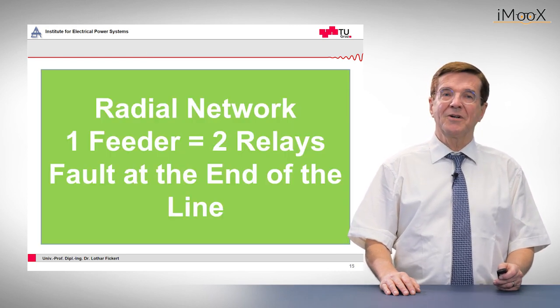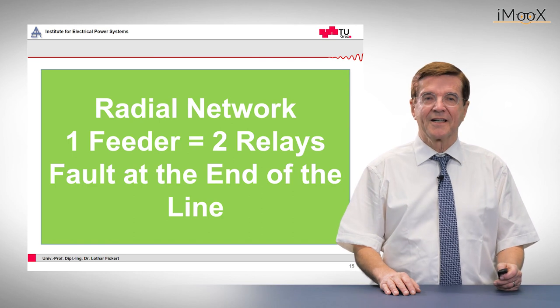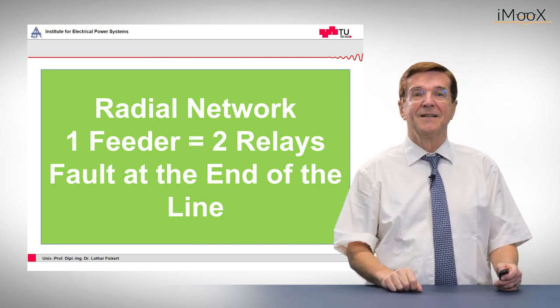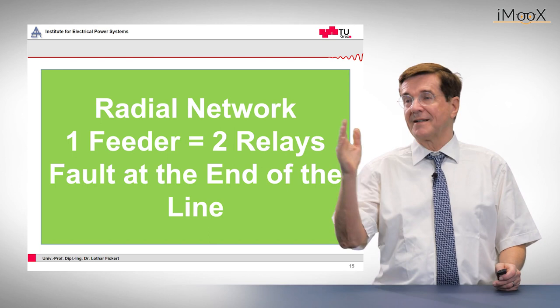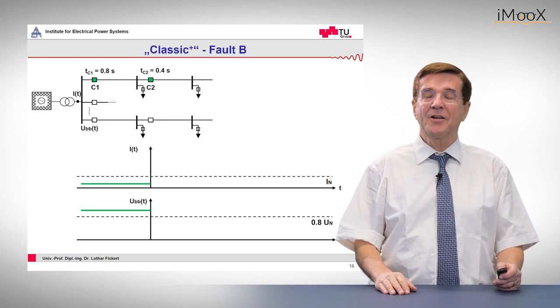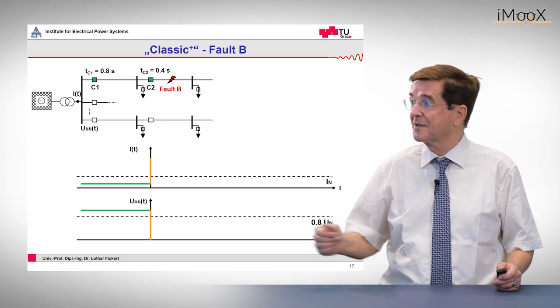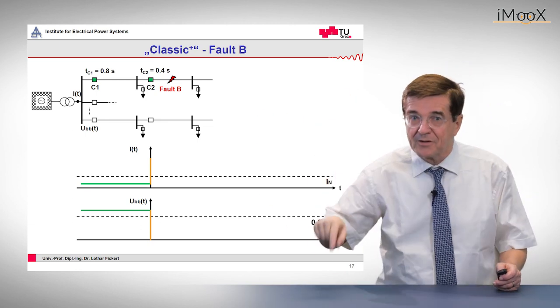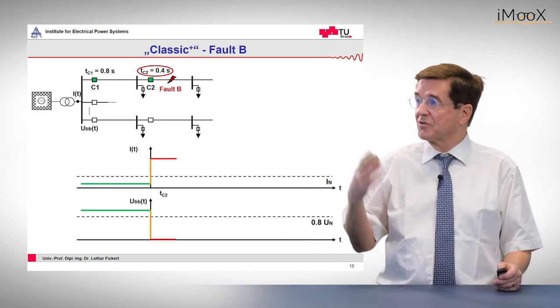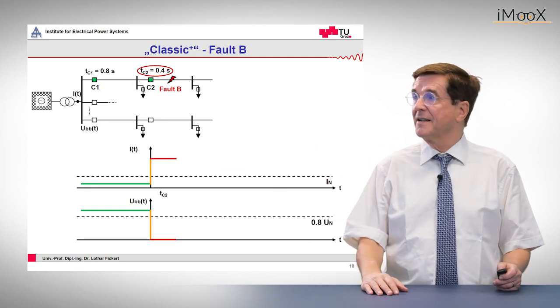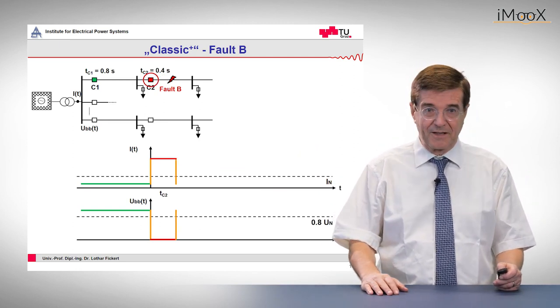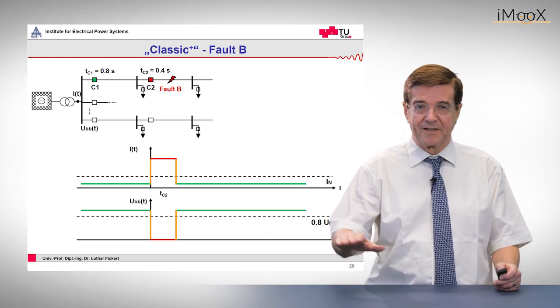Now if we want to have a more sophisticated approach, we take one feeder but two relays: one at the beginning of the line, the other one at the end of the line. And we look again at the fault at the end of the line. The fault occurs, the current goes up, the voltage goes down, and this goes on for 0.4 seconds again. After this, the fault is cleared, the circuit breaker opens, and the system resets.